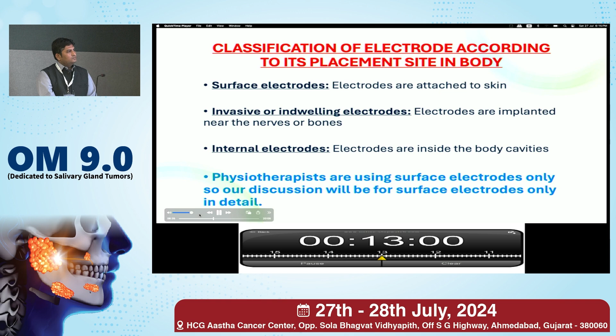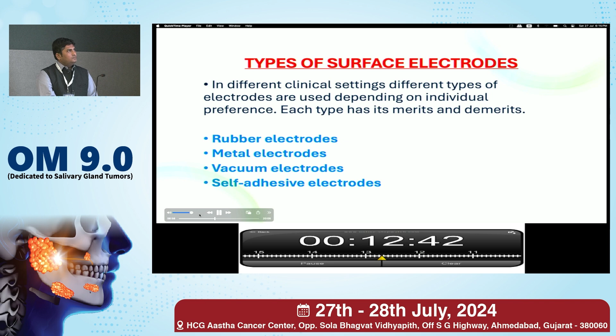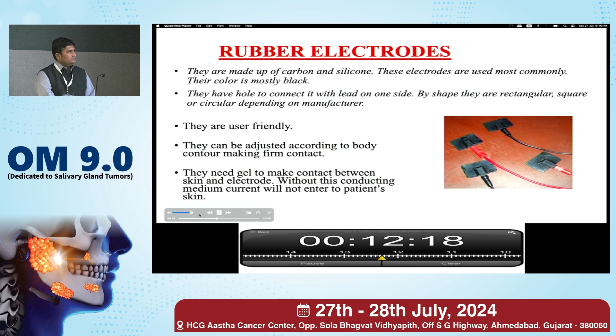Coming to the types of surface electrodes used in physiotherapy, they are rubber electrodes, metal electrodes, vacuum electrodes, and self-adhesive electrodes. We will now discuss in detail each type of electrodes. Rubber electrodes. They are made up of carbon and silicone. These are the most commonly used electrodes, and their main advantage is that they are user-friendly and they can be adjusted according to the body contour, making firm contact with the skin. They need gel to make contact between skin and electrode. Without this conducting medium, current will not enter the patient's skin.